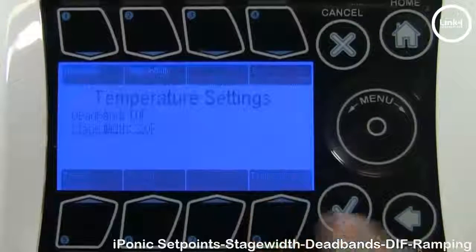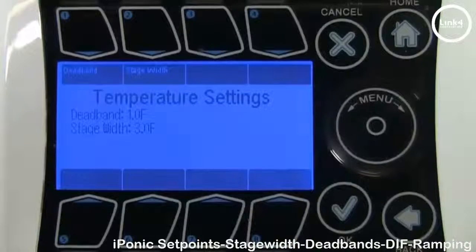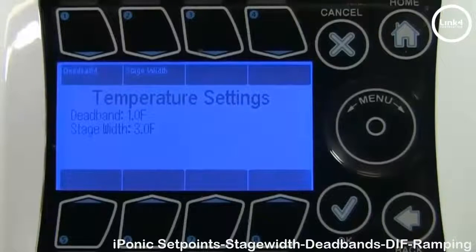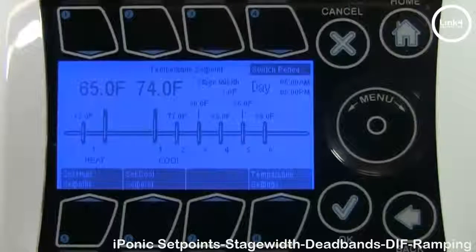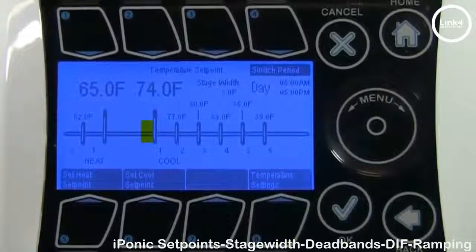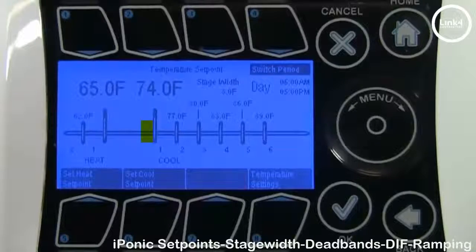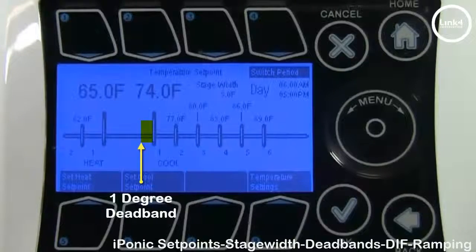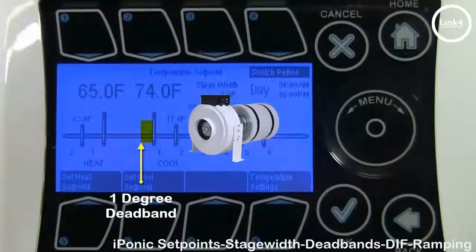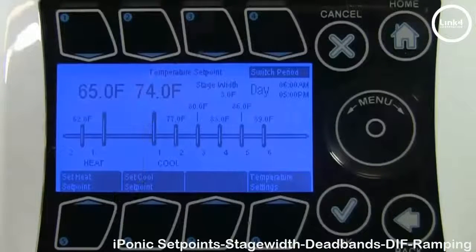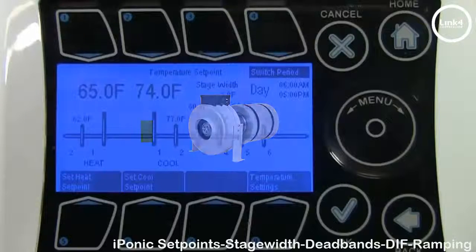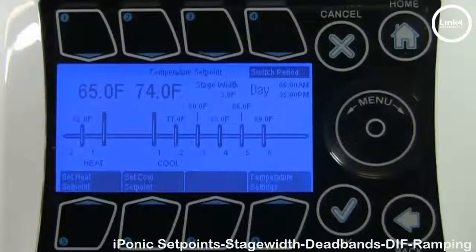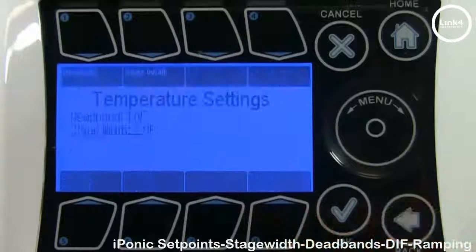Button number 8 gives you the option to change your temp settings. Right now your stage width is at 3 and the dead band is at 1. When the temperature rises above the cool set point, the system remains in cool stage 1 until the temperature drops below the dead band. The dead band prevents equipment from oscillating on and off continuously, keeping the temperature of the environment within its new stage. Note: the stage width must always be wider than the dead band.